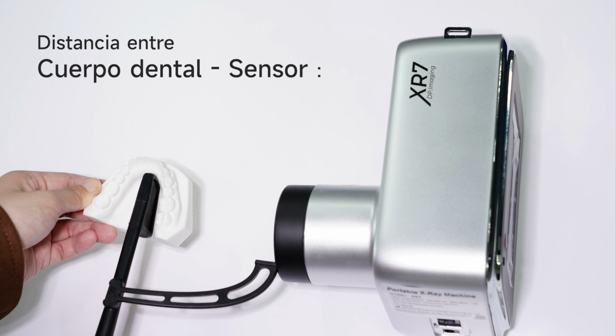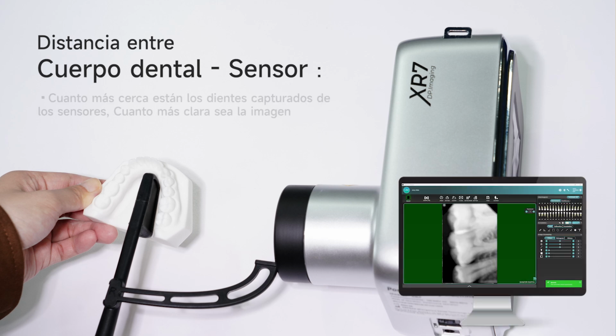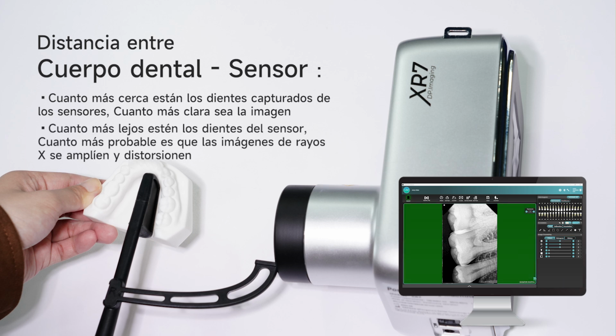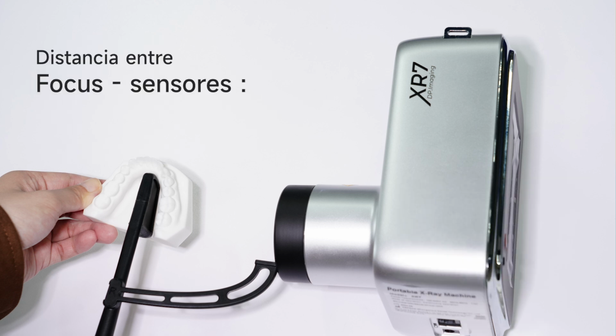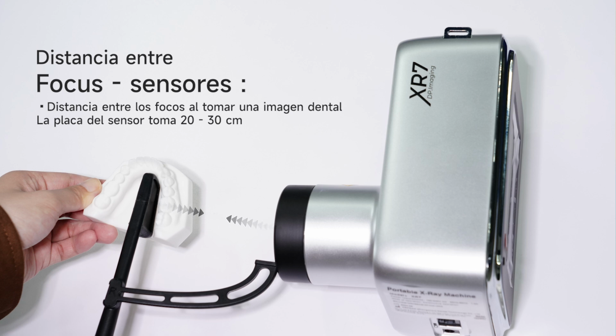Distance between tooth body and sensor. The closer the capture tooth is to the sensor, the clearer the imaging. The farther the teeth are from the sensor, the more likely the X-ray image is to be magnified and distorted. Distance between focus and sensor. When taking dental image, the distance between the focus and the sensor plate is taken as 20 to 30 cm.